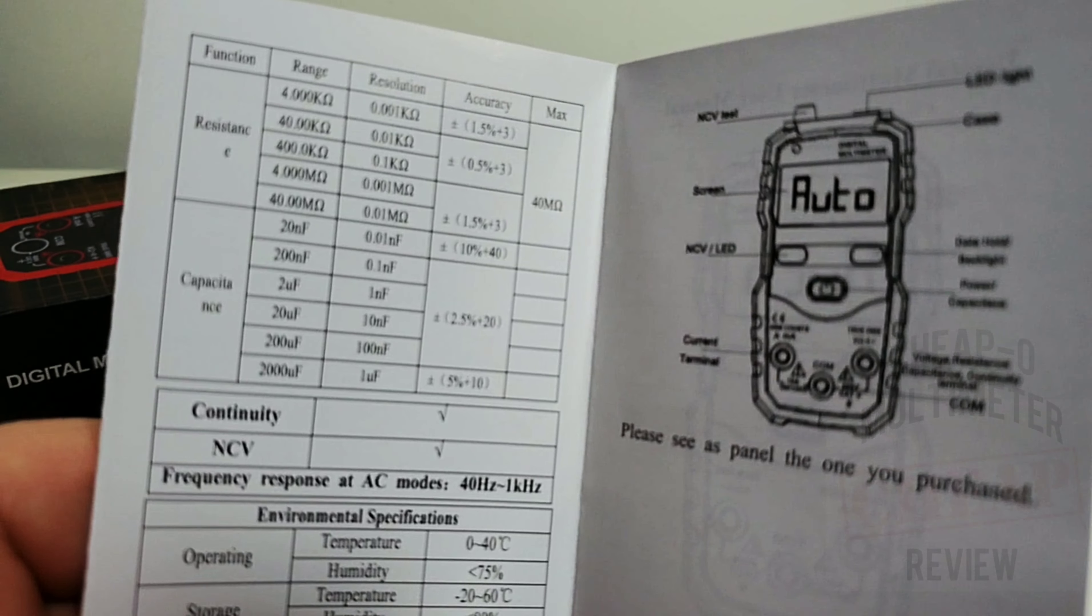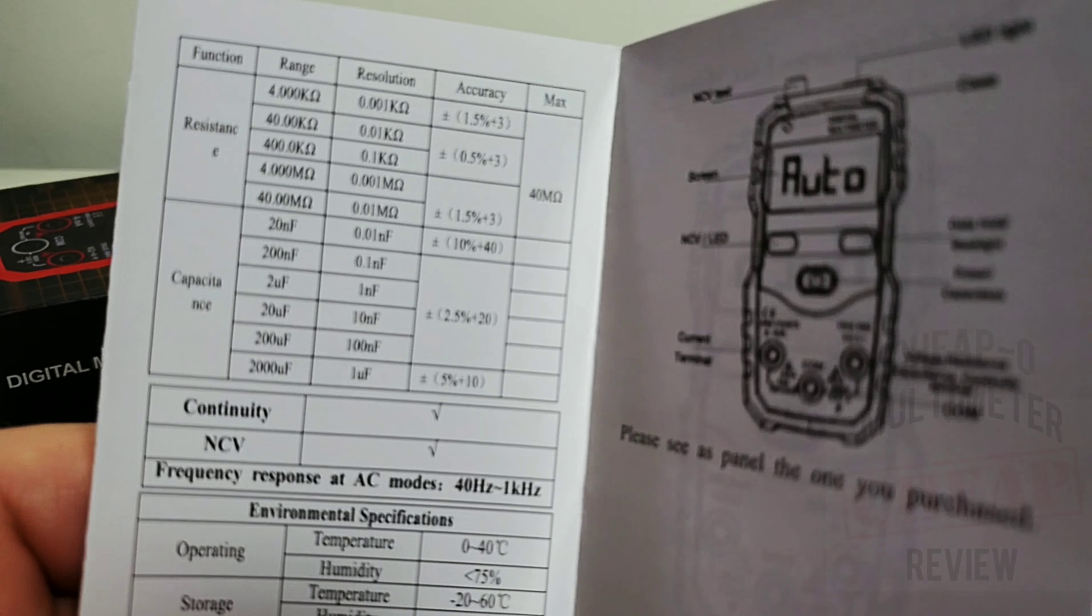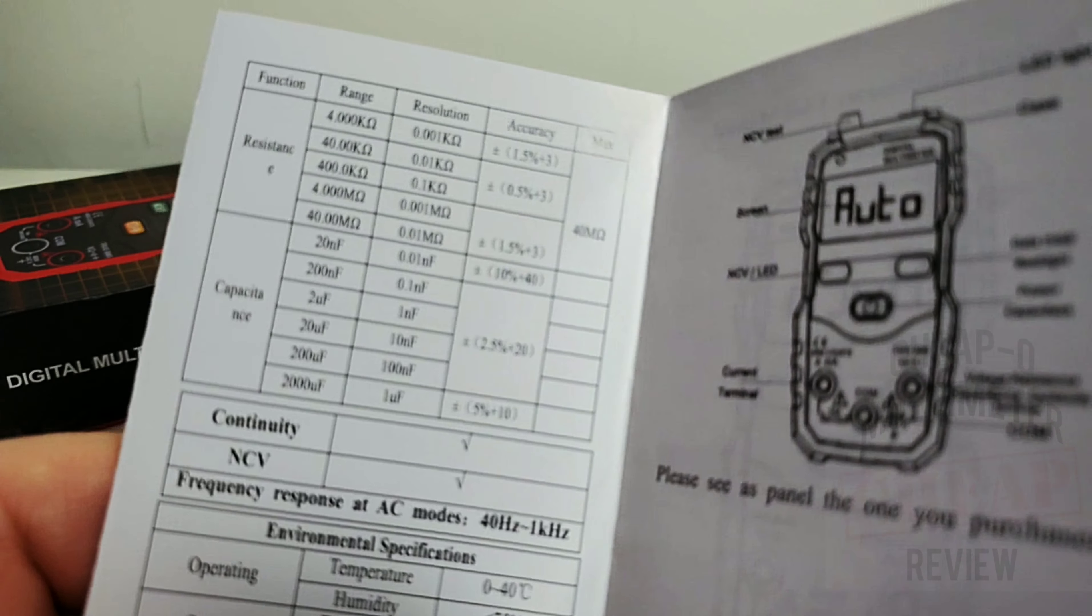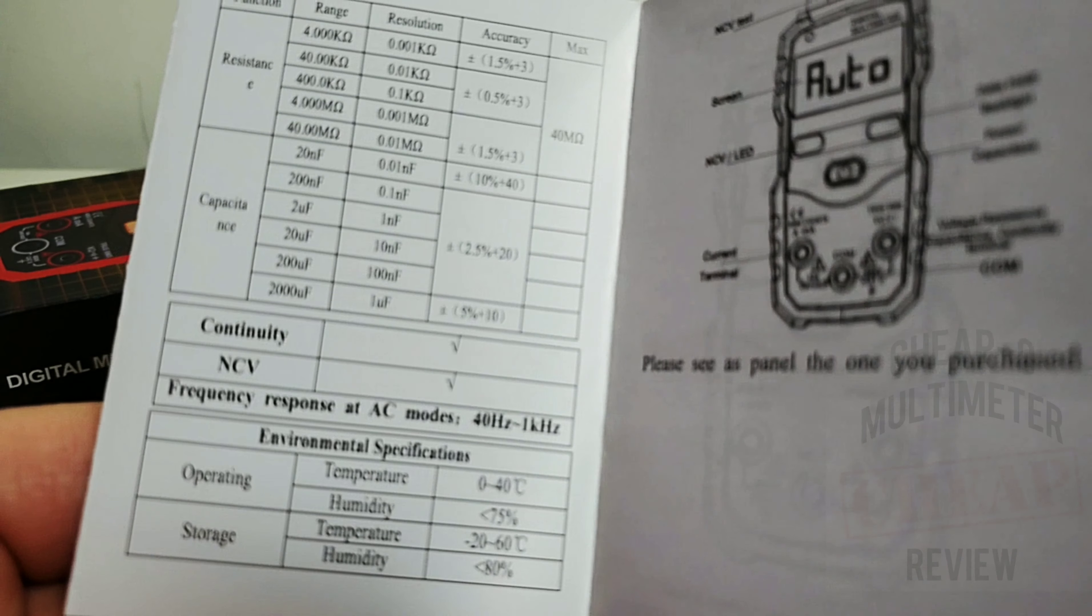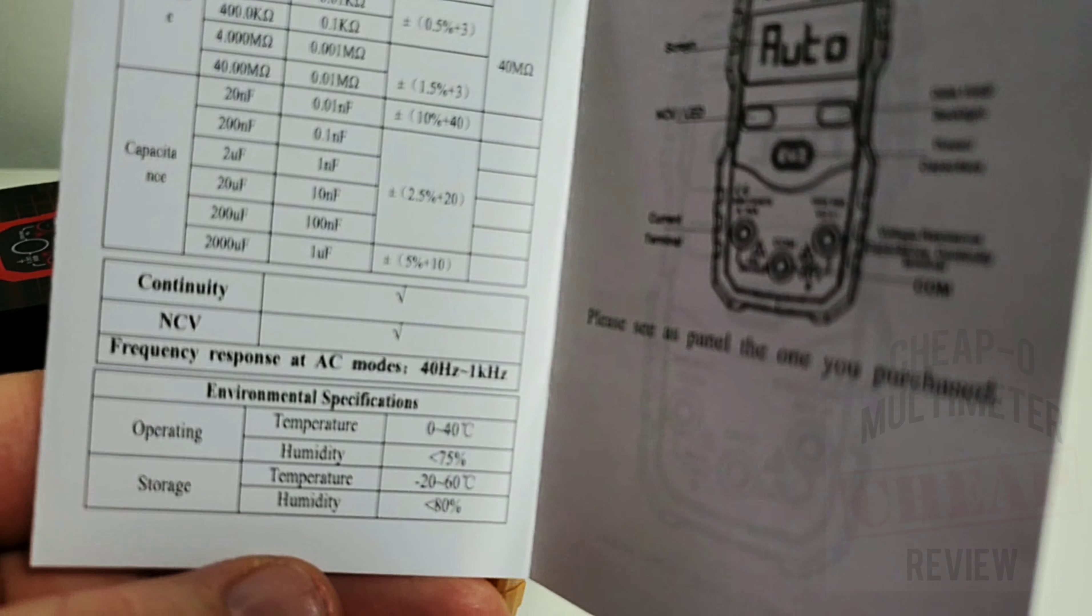Resistance 40 megaohm, that's decent I guess. Definitely would like to see at least 60, maybe 100 megaohm would be optimum, but there you go.